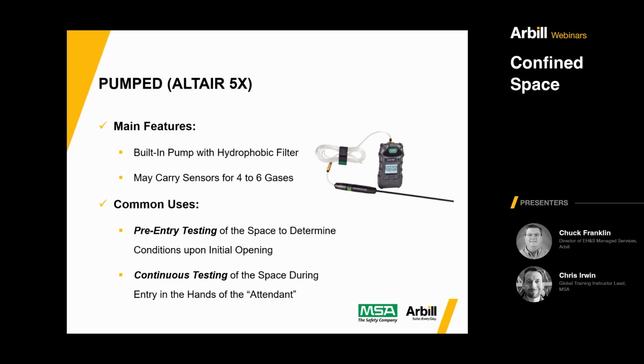That said, you want to be careful not to let the line dip in water, because that filter will, from my experience, take a long time—weeks—to dry out. So it's good to have extra filters on hand so you can pull the wet one out and put a new one in. But even better, don't let the line dip into water, because we're trying to protect the sensitive electronics inside the instrument.